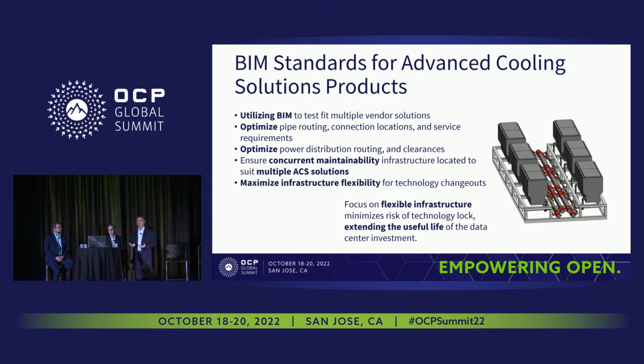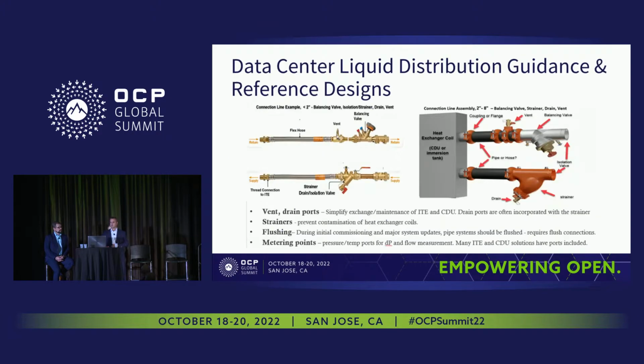One of the reasons we're using groove piping solutions is because it's very easy, if you need to change the size of a tap on your header, to close your segmentation valves on your concurrently maintainable loop and disconnect your groove couplings, pull a T out, put a new T in, you're done, no hot work in the space, and so on. So that's part of our emphasis on flexible infrastructure and extending the useful life.